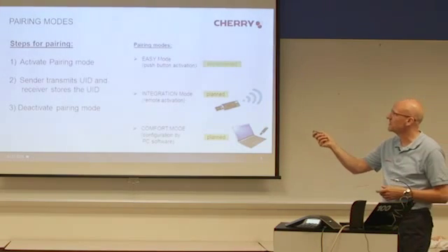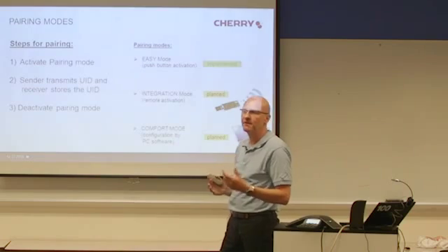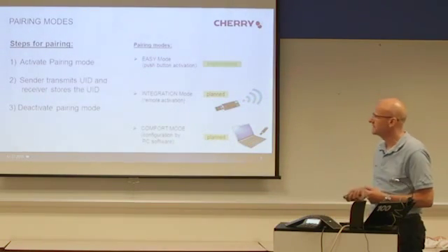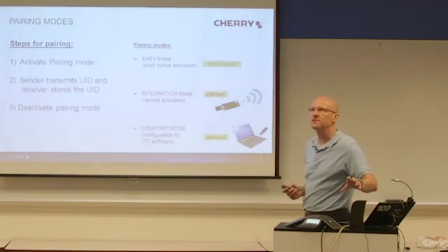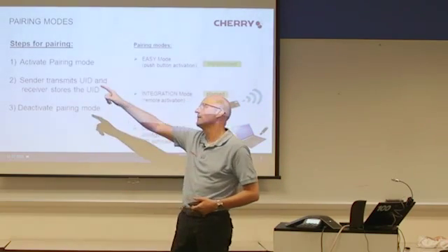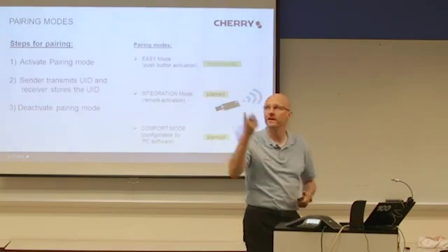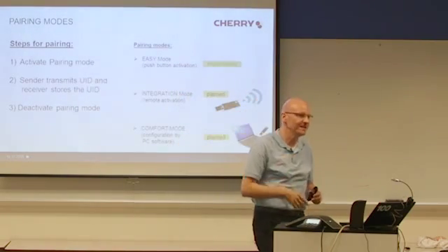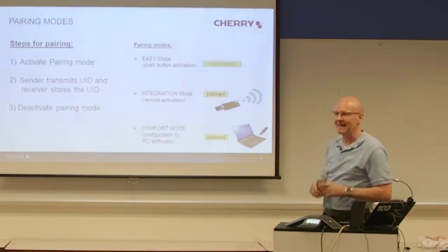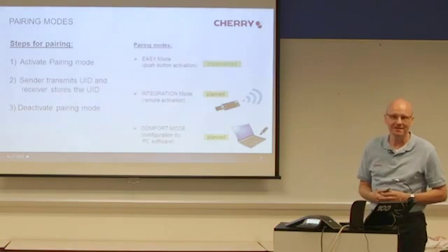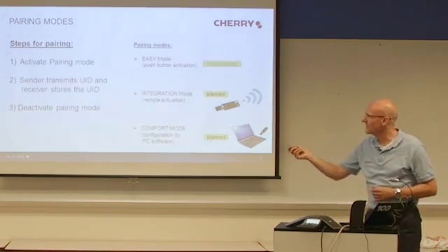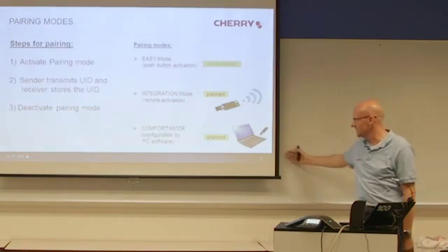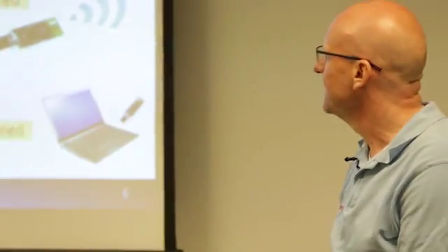The easiest way to activate the pairing mode is to put a switch on the receiver and press it — we call this 'easy mode': pairing by push button. But what if the receiver is placed behind a wall or in the ceiling and you cannot reach it to press a button? Then you need a way to activate the pairing mode without touching the receiver. We call this 'integration mode,' because the receiver is integrated behind a wall or in the ceiling. One option is a USB stick connected to a computer.